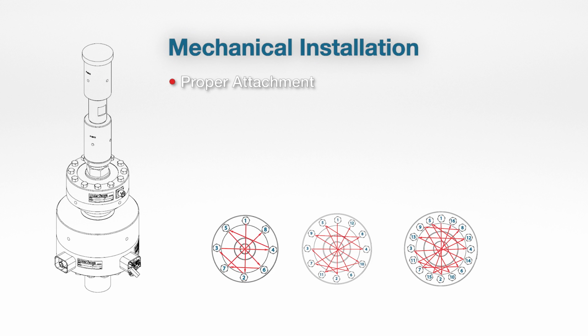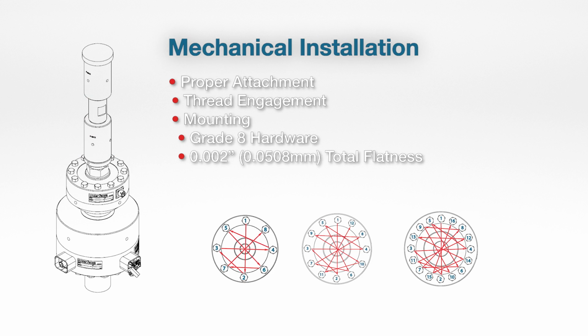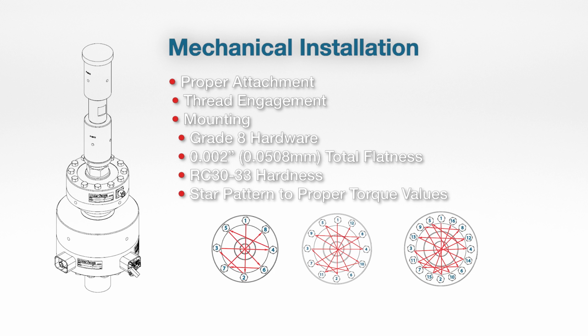So, mechanical installation: you've got your load cell, you've got it hooked up, you've got your instrument scaled, now you want to get it installed and start using it. Well, there are some things you want to follow from a mechanical attachment standpoint. You can see here is the production unit on one of our cal frames, not quite painted up yet. We've got it threaded in there. You want to make sure when you're threading into what we call the live end of the load cell, which is the center hub on the LP, that you've got enough threads engaging into the load cell itself.